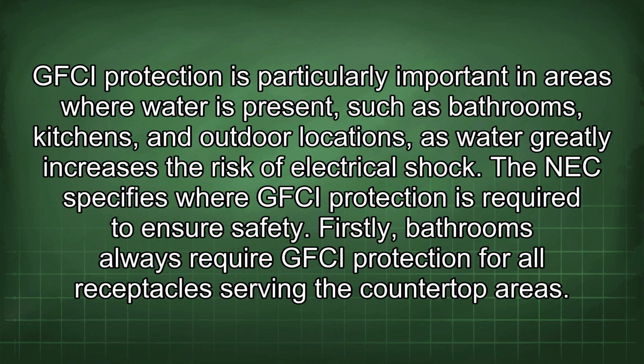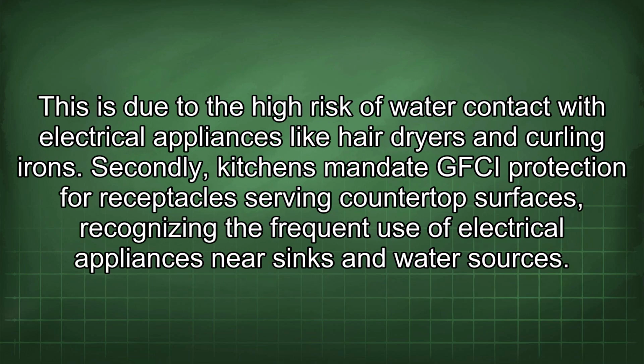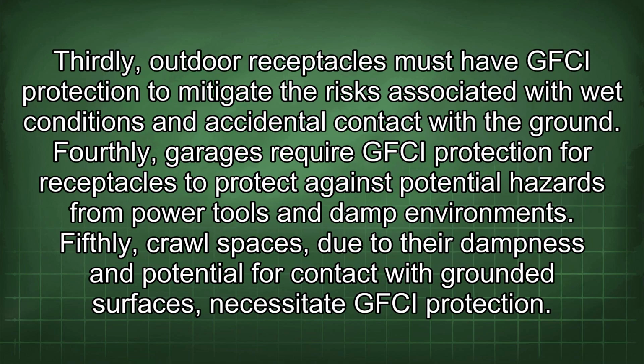The NEC specifies where GFCI protection is required to ensure safety. Firstly, bathrooms always require GFCI protection for all receptacles serving the countertop areas. This is due to the high risk of water contact with electrical appliances like hairdryers and curling irons. Secondly, kitchens mandate GFCI protection for receptacles serving countertop surfaces, recognizing the frequent use of electrical appliances near sinks and water sources. Thirdly, outdoor receptacles must have GFCI protection to mitigate the risks associated with wet conditions and accidental contact with the ground.